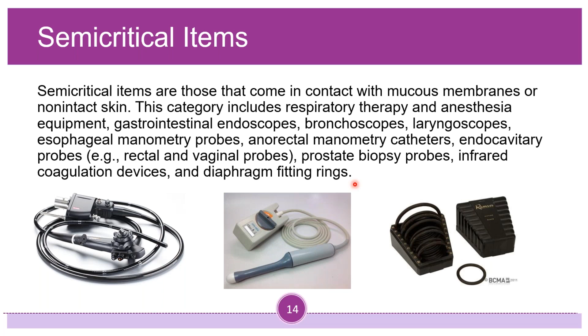These medical devices should be free of all microorganisms, so mycobacteria, fungi, viruses, and bacteria, although small numbers of bacterial spores may be present. Intact mucous membranes, such as those of the lungs or the gastrointestinal tract, generally are resistant to infection by common bacterial spores, but are susceptible to other organisms such as bacteria, mycobacteria, and viruses. Semi-critical items minimally require high-level disinfection using chemical disinfectants. Some examples: glutaraldehyde, hydrogen peroxide, OPA, improved hydrogen peroxide, peracetic acid with hydrogen peroxide, and chlorine-based products are cleared by the U.S. Food and Drug Administration and are dependable high-level disinfectants provided the correct parameters for time and temperature.